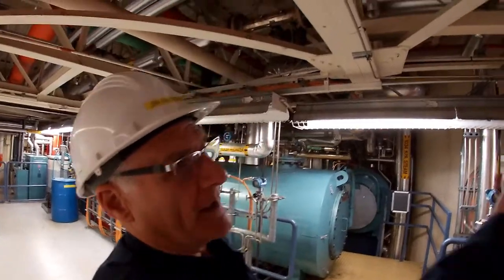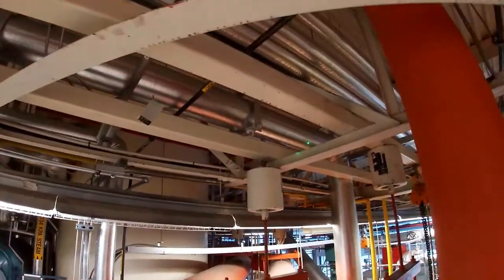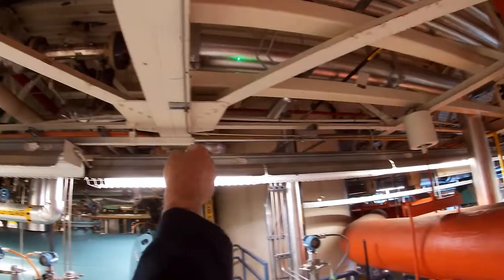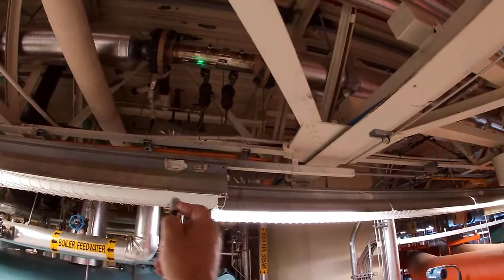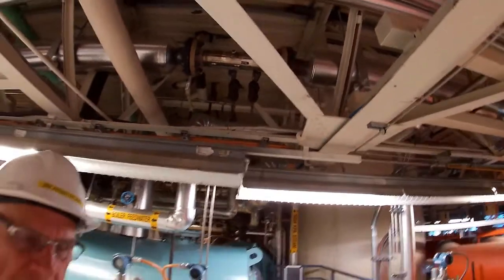So now we're up on the roof, above the control room on the mezzanine floor. Following my laser, there is the steam line — the 250 pound or 1725 kilopascal steam line coming along — and right here is a machined venturi tube which is actually measuring the steam flow to the turbine.